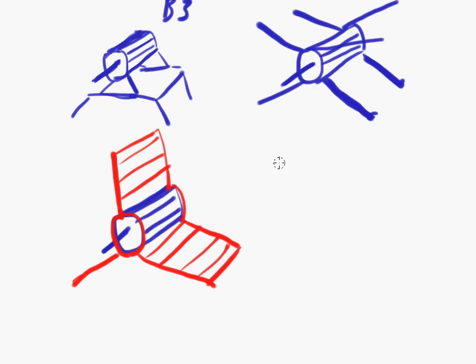And those are like vanes in the airflow. And what they do, air would come like this, drawn by the impeller attached to the shaft. Air would come like this, go over those vanes, also acting as motor attachments. Thus, those vanes would clean up that turbulence of the air, and thus deliver a much less turbulent air to the impeller than with that setup. So basically, the motor attachments are not only attaching the motor to the casing, but also acting as guide vanes, which are cleaning up the air of turbulence before having that air reach the impeller.